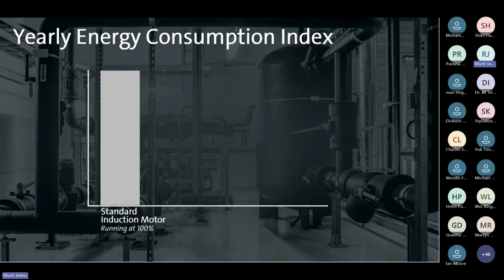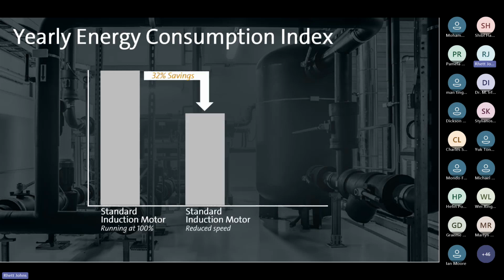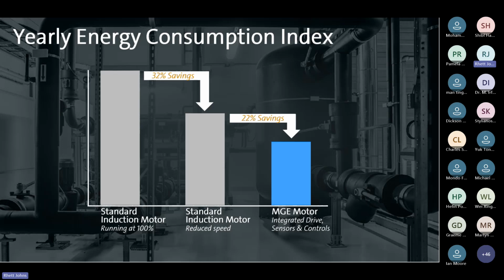When we look at the yearly energy consumption index of a pump system, if you're running your pumps at 100% load, standard fixed speed motor, you're going to be consuming 100% of the potential energy consumption on that system. If you then add in your standard induction motor and you have a reduced speed, so you tune the pump speed in order to run it at the required pressure of the system, but you don't add any more controls, you've got a pump that's running at a lower speed, and you can get 32% of your savings that way. The next step for 22% savings, you would need to go towards that IE5 motor efficiency, but also start looking at adding in sensors and controls in order to efficiently ramp up and ramp down the motor operation in order to run the pump according to the required flow and head that it needs within the controls. So that really gives you your full scope of savings when we look at optimizing a pump system.